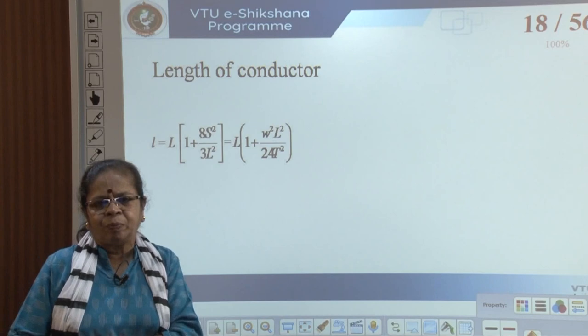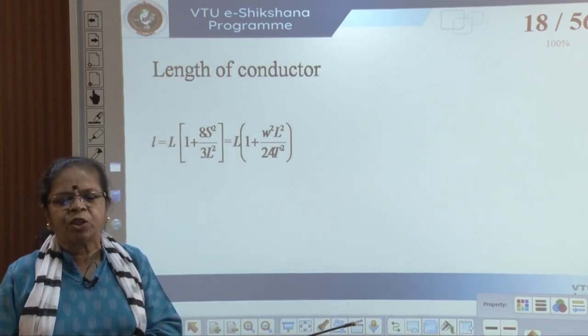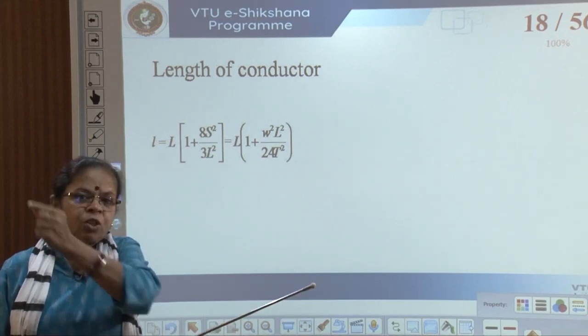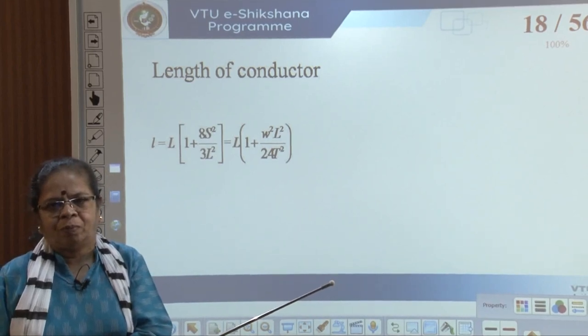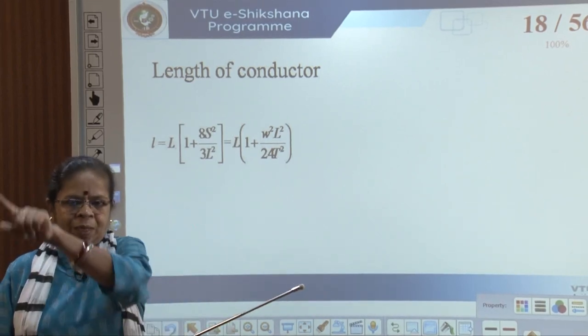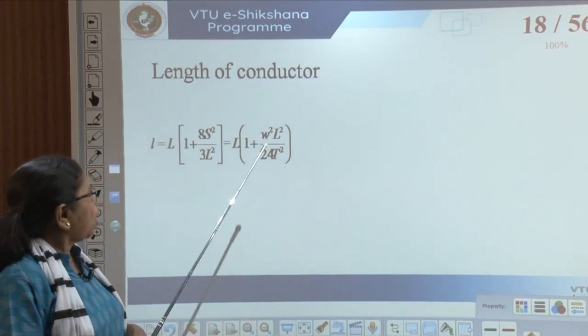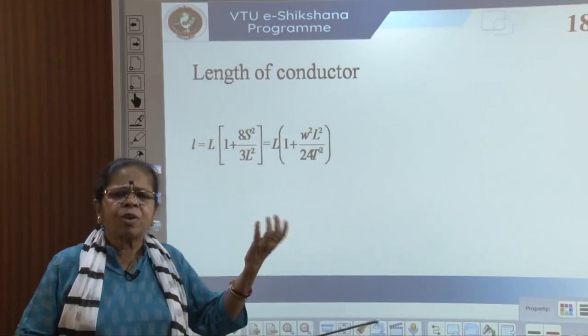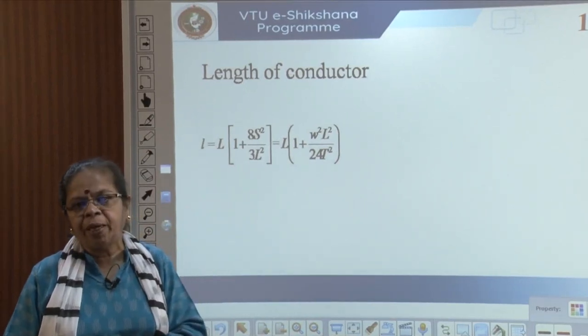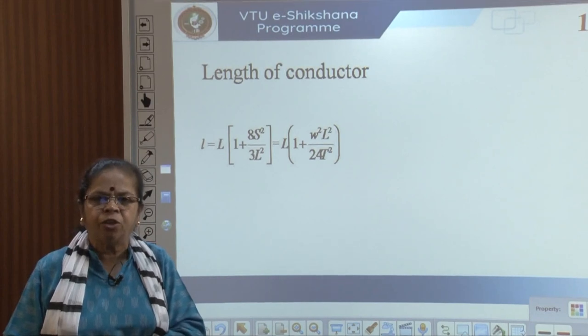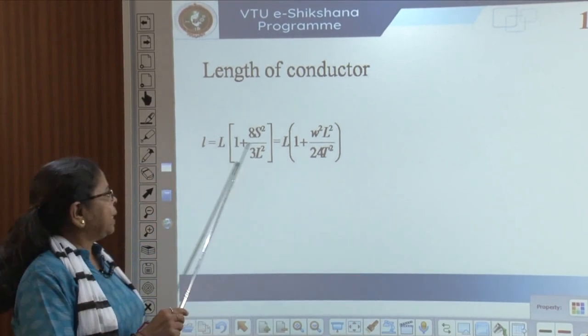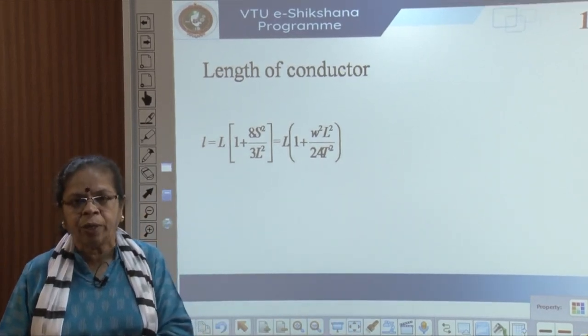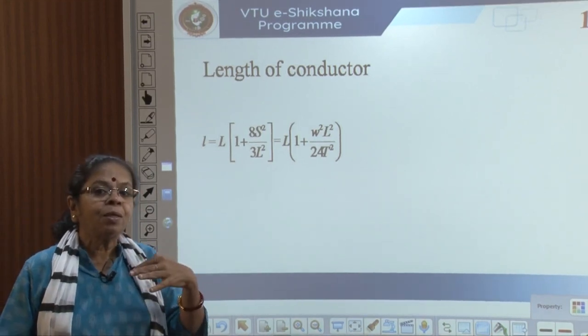Since it is a catenary, there is a formula for the total length of conductor required. From the equation of a catenary, the length is approximately given by L(1 + 8S²/3L²). This will give you an idea of how much conductor length is actually required when you make provision for the span.